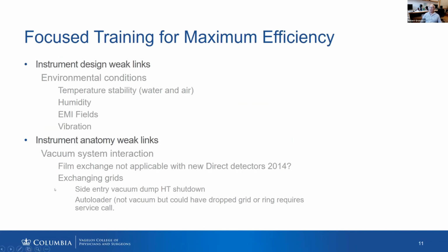The focused training that we do is to address or stress the weak points of the microscope, or the actual environmental conditions. Lots of money is spent on getting the environmental conditions perfect: the water and air temperature stability. We often find that a problem with the condenser water in the building will raise havoc on our systems. The humidity as well.